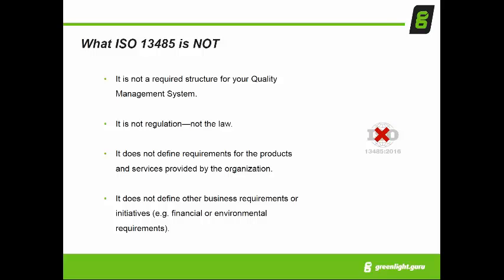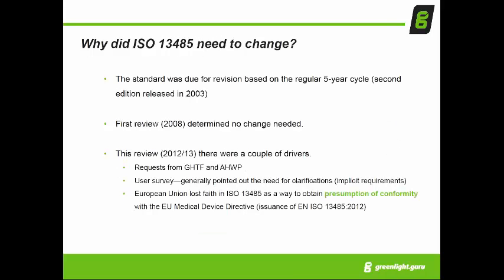Okay, thank you. I'll let you continue, and I'll note that one participant, JP, notes it's not required for the U.S., it is required for CE marking and distribution to the EU and other places that accept the CE mark. It's a generally accepted best practice. There are parts of the world where ISO 13485 is required. There are many parts of the world where we assume it's required, but it's not technically.